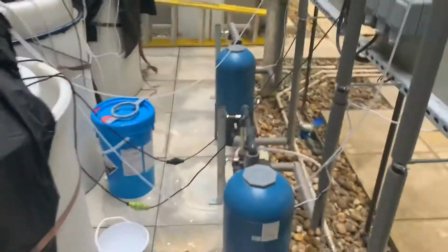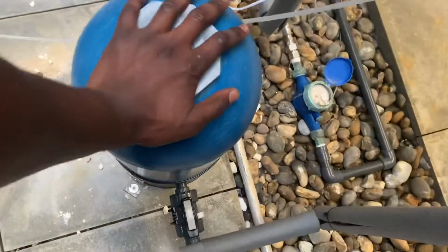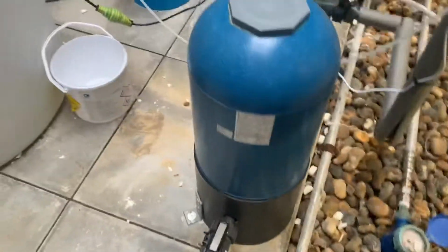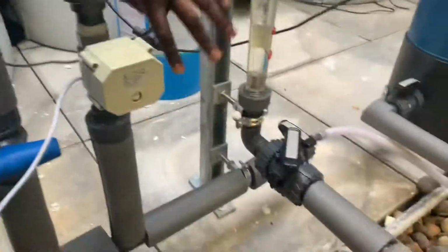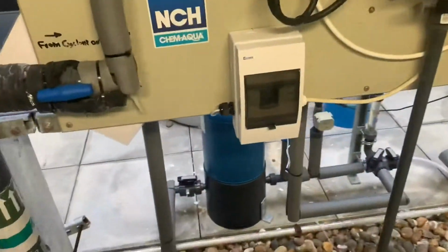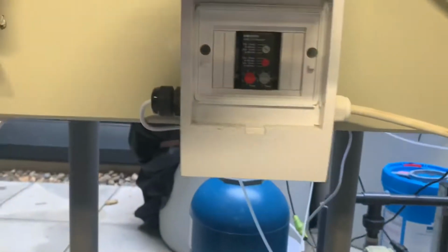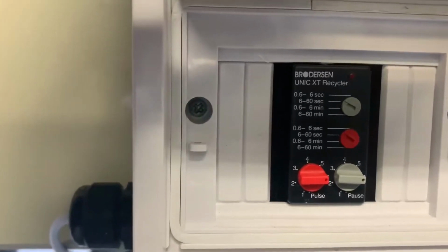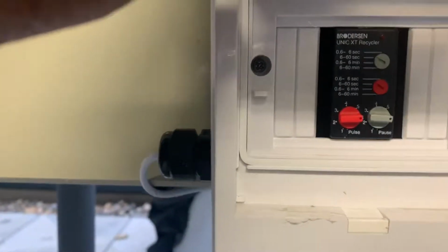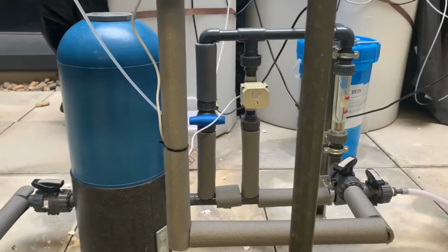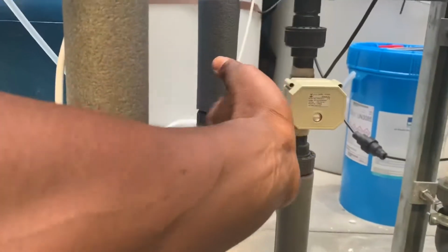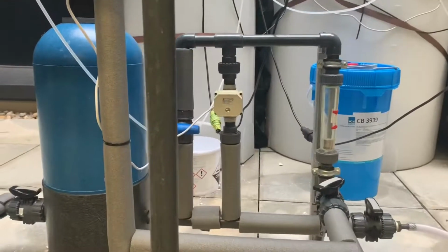And if we go around the back, we can see that we have our bromine. Some of us might still be using chlorine. It's the same type of system, but bromine is just in a tablet form. I will show you what it's like later. So the bromine goes into our system over here, through this dial over here. And the system we've got made at the moment is a pulse system. So it works upon how many pulses we want per minute. So it will stay open for 2 to 4 or however much you require it to do so. So this is the solenoid valve for that pulse system, which is here, which goes along and is fed here. So that's the solenoid valve. I'm sure we all know what the solenoid valve does, opens and closes.